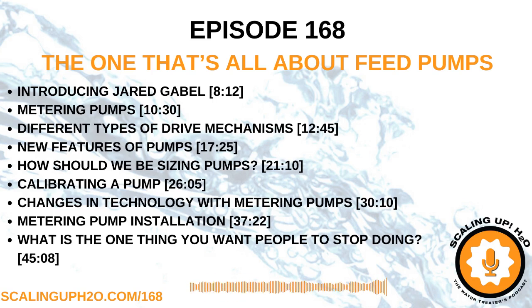But all the while, I'm still pushing out the chemistry at 100% stroke length to get that entire volume displaced in the dosing head. And that really helps us to keep the pump from vapor locking and requiring multiple priming frequencies. That's a great tip. I'm sure we've helped a couple of people out there that are troubleshooting that problem as we speak.